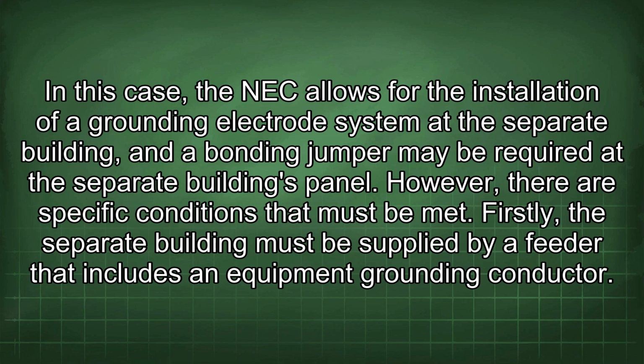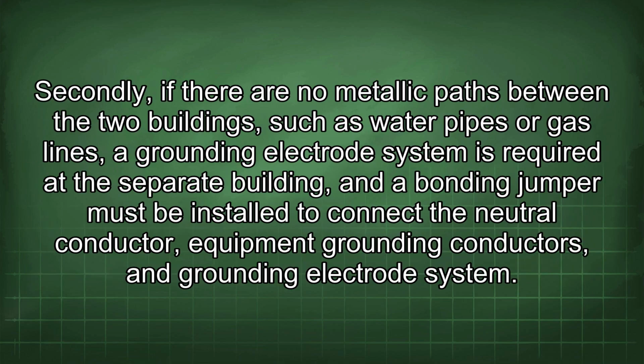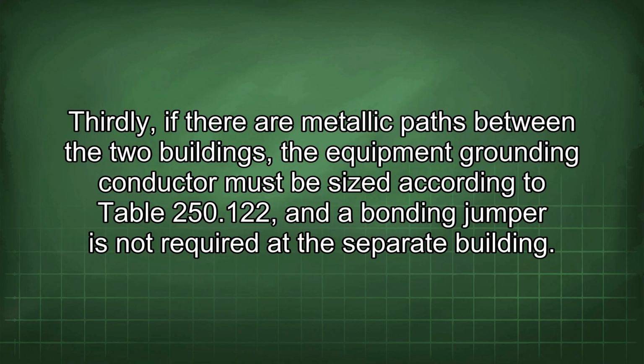Firstly, a separate building must be supplied by a feeder that includes an equipment grounding conductor. Secondly, if there are no metallic paths between the two buildings, such as water pipes or gas lines, a grounding electrode system is required at the separate building, and a bonding jumper must be installed to connect the neutral conductor, equipment grounding conductors, and grounding electrode system. Thirdly, if there are metallic paths between the two buildings, the equipment grounding conductor must be sized according to Table 250.122, and a bonding jumper is not required at the separate building.